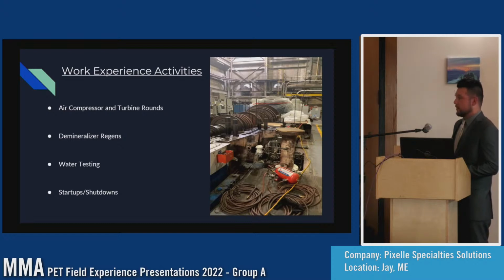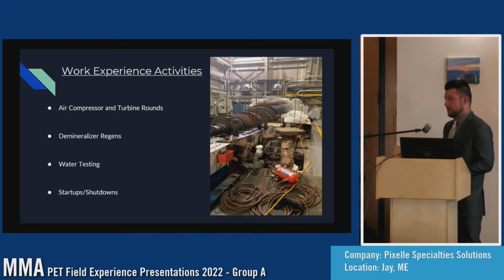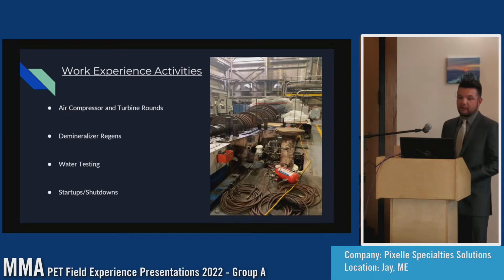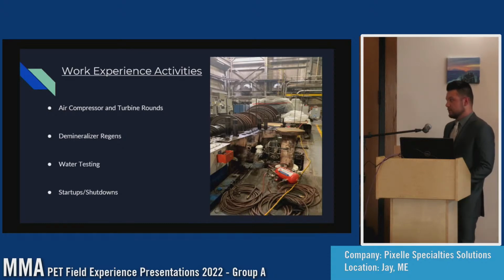For the demineralizer regens, usually the demineralizers would break due to high silica levels. So if that happened, then we would need to valve out one, valve out another one, or valve in another one, and then perform a regen, basically a rinse down on the demin that broke. Water testing, I mean, we tested the turbine condensate, condensate from the paper machines, and we tested for hardness, conductivity, silica, pH.